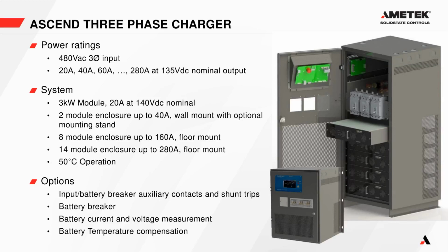We offer 3 separate enclosures for the 3-phase Ascend. We have a 2 module enclosure, which holds 2 modules and up to 40 amps output. This is a wall mountable charger, and we can also provide a mounting stand, so it can be mounted on the floor and sit at like 36 inches high. We also offer an 8 module enclosure. It is up to 160 amp output, and it's floor mounted. And then we offer a 14 module enclosure, which is 280 amps, and it's also floor mounted. I will provide the sizes of those cabinets later in this presentation.